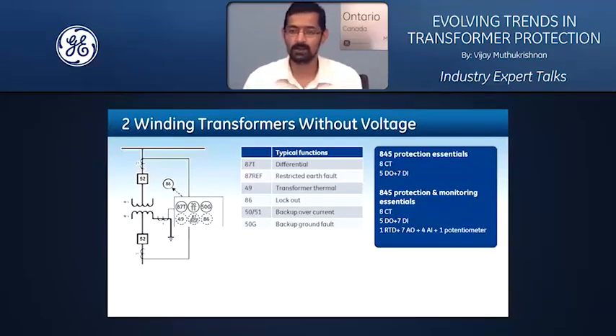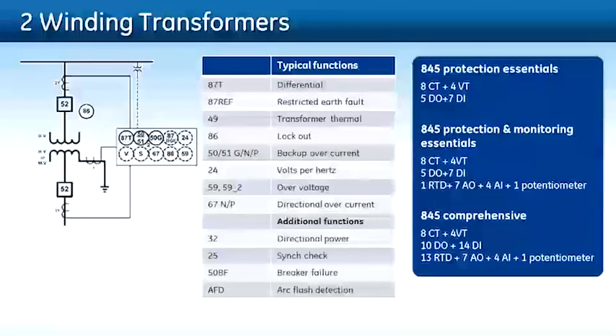If you want to add a little bit of monitoring functionality into your transformer protection relay, you can definitely add the low voltage analog card module that brings in DC milliampere inputs and outputs with RTD inputs. So that gives you a base level of monitoring functionality for a transformer application like this. The next one is the same two-winding transformer application, but with voltage input coming into your transformer protection relay. This again varies all the way from medium voltage, and is more common in transmission and sub-transmission applications.